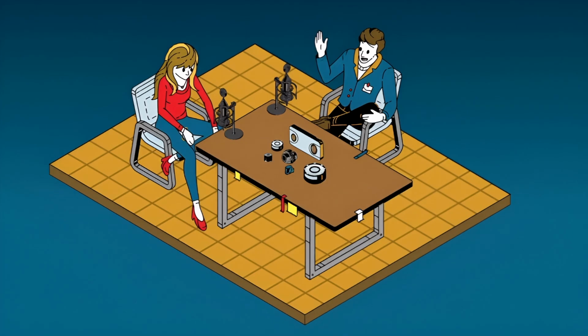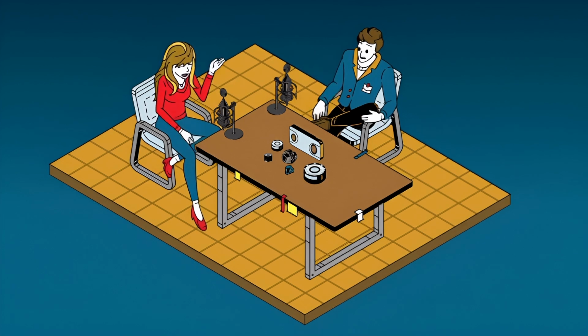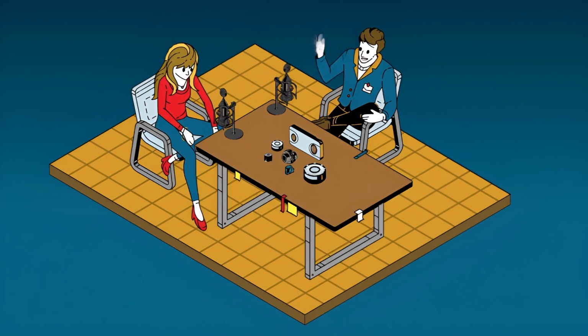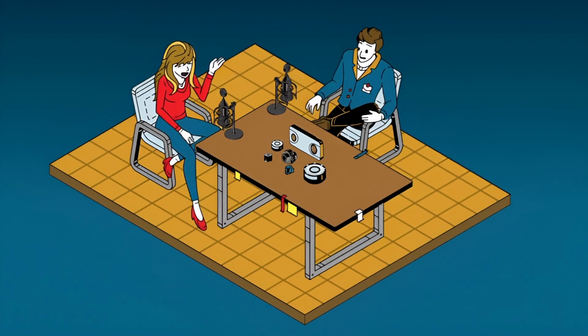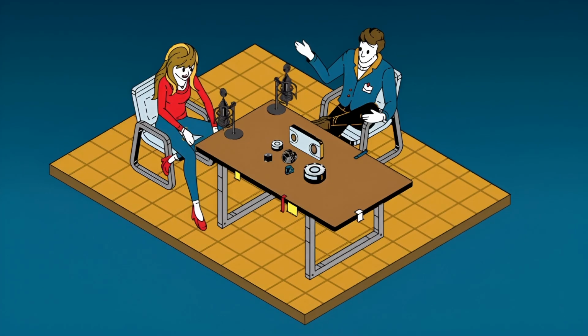Okay, that makes sense. But if you take that S-type and put it 2 miles underwater on a deep-sea drilling rig... Oh, the pressure would be insane. Exactly. The crushing hydrostatic pressure of the ocean pushes on it from all sides equally. That would corrupt the data and potentially just destroy the sensor. So a submersible load cell has to be structurally compensated to ignore the pressure of the ocean. Right. And only measure the mechanical force of the drill itself. Exactly. They are hermetically sealed, usually in heavy stainless steel, and internally pressurized or potted. So the extreme environmental pressure becomes a total non-factor.